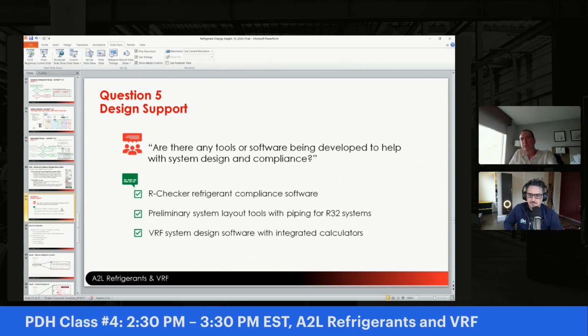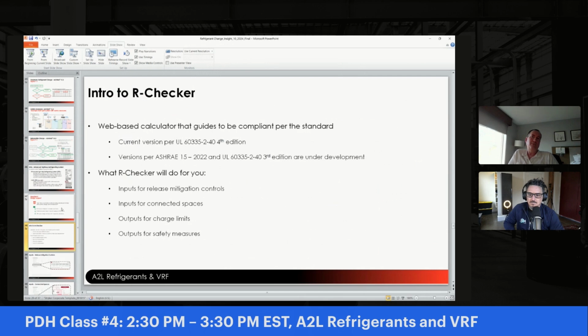Looking at R Checker, this is a web-based calculator that helps you be compliant. It's currently set up per the fourth edition of UL, but we're working on versions for ASHRAE and the third edition of the standard as well. R Checker gives you a place to put inputs for your release mitigation controls and your connected spaces, and then you get outputs for charge limits and safety measures, which is kind of nice.